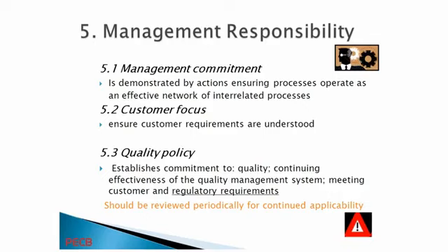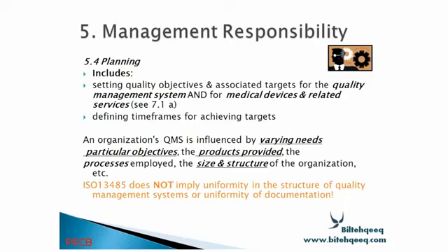Development of the quality policy: the main focus of the quality policy is the fulfillment of the customer requirements as well as the regulatory requirements. And the quality policy should be reviewed periodically for continued applicability. 5.4 is planning, which includes setting quality objectives and associated targets for the quality management system and for medical device related services, and defining time frames for achieving targets. So we have to plan and set the targets, and we have to describe in what way we will be able to achieve these objectives.